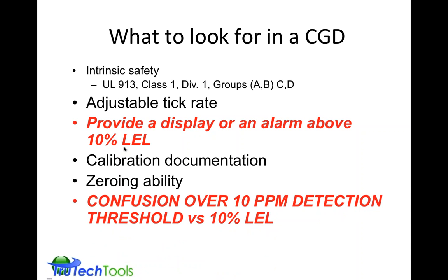There's also, for a period of time, and this was maybe 18 months ago, but I heard it a lot, people were confused when they heard a 10 ppm detection threshold was being used. I believe some states were requiring gas leak detectors that were as sensitive as a 10 parts per million detection threshold. And some people were confusing that with 10% LEL in terms of alarm or display level. And those two are very different. So detection threshold and LEL readout or alarm are two different things. You can have a sensitive detector, but it doesn't display any level on it. I want to make sure people understand that difference.